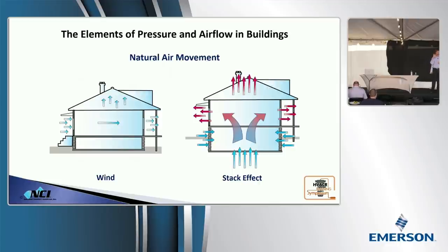They were going backwards. Every heat exchanger has a pressure drop to it. So for air to come down the flue, overcome the pressure drop of the heat exchanger, and then go out the burner openings, that's a lot of depressurization, and it can happen. Now, with two 20 by 20 openings, shouldn't that have been enough combustion air? You would think so. But for whatever reason, wind, the air wanted to come down.